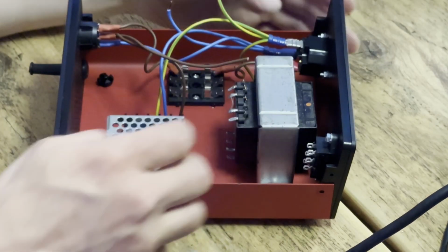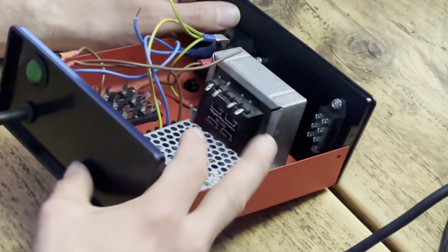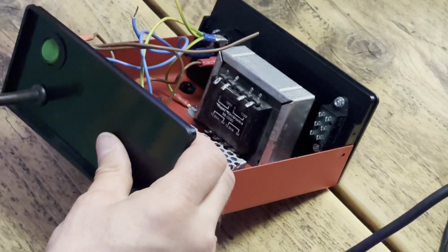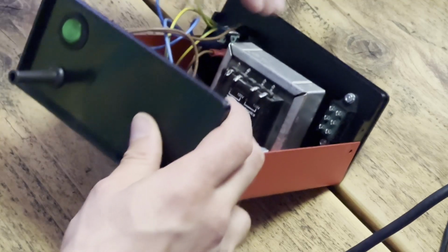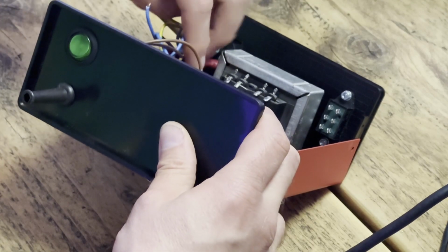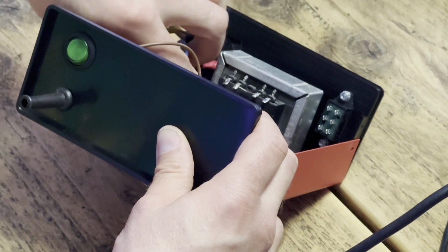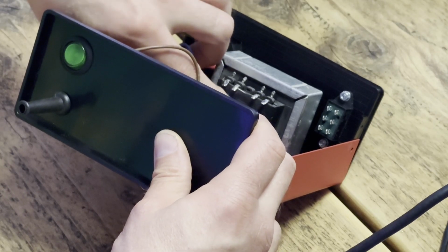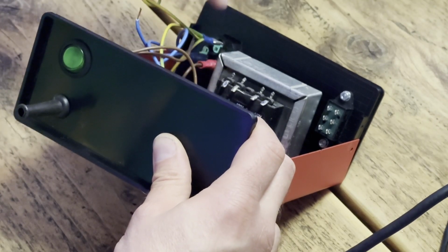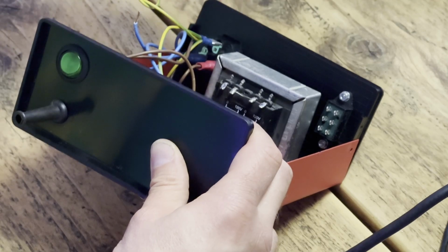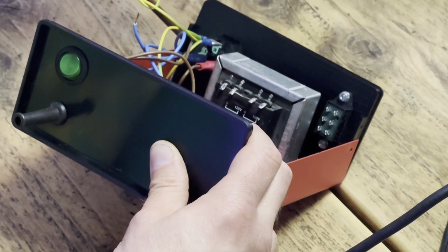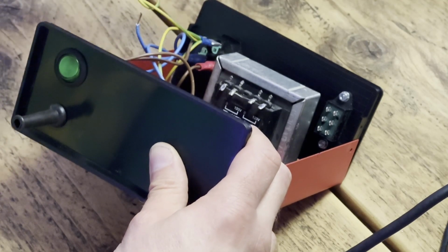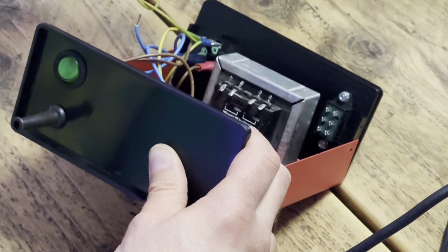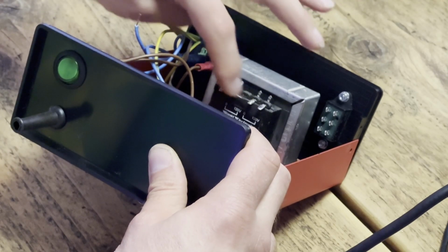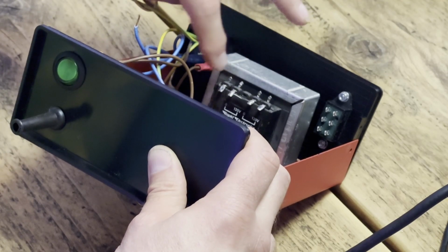But with the transformer, this is a particular type known as a dual primary transformer. And if you look carefully down here, it says it's got 2 connections, both from 0 to 120 volts. This can be wired in 2 ways: either connected for 120 volts, or connected for 240 volts, which is the way it's been wired now. So someone has previously used this transformer.